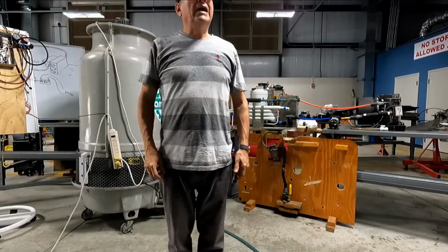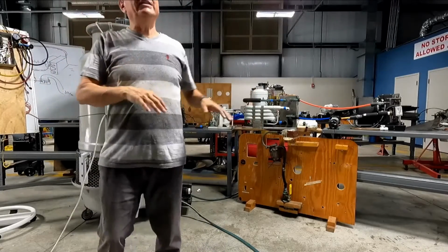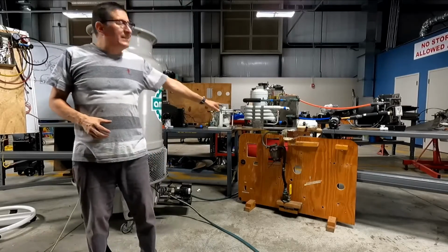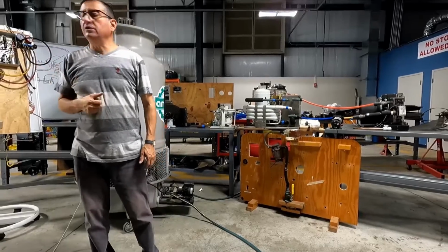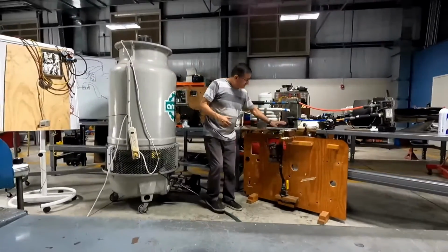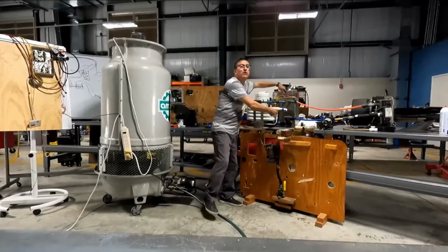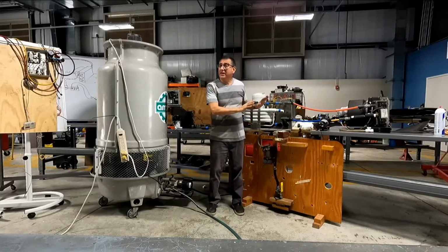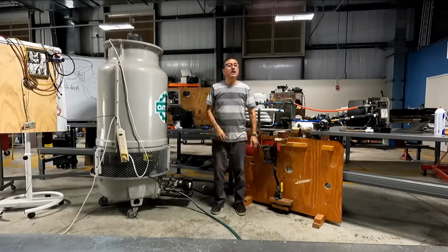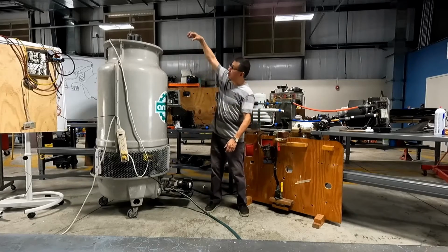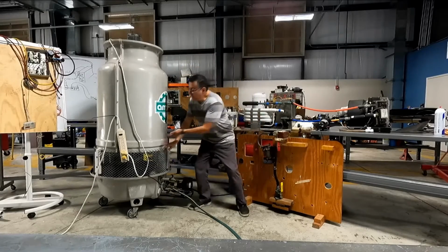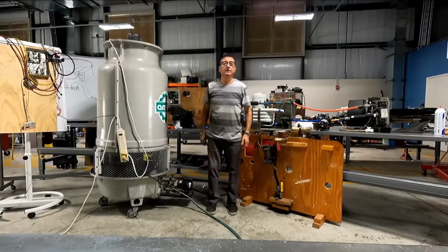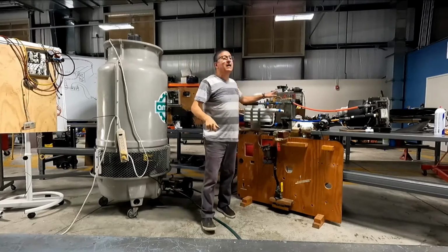And okay, what is the element that you need to isolate in the regular unit when you connect the cooling tower? The compressor. No, isolate the raw water system. Oh, the raw water system. You need to eliminate this connection and connect the cooling tower here. Start the cooling tower before you start the air conditioning. Verify that the water returns, the water goes up and goes down, and verify with your hand that the water coming down is a little warm. Okay, that's okay. It's circulating. And after that, you enter the boat and you start the air conditioned unit.